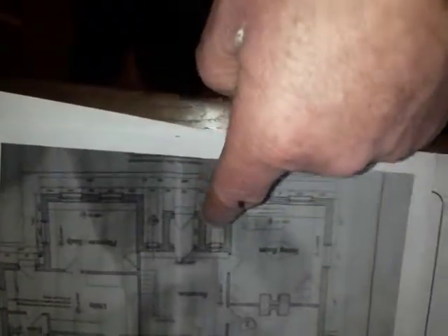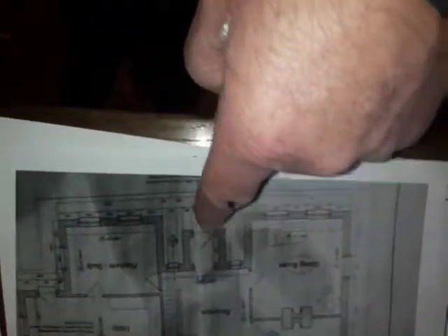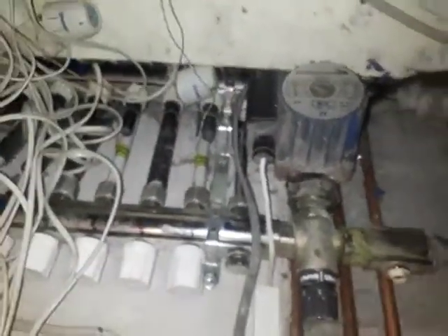Once from the temperatures we determine where the loop is actually heating in the house, we will mark that on the manifold with a permanent marker. So for example, if loop 1 for instance was the playroom study, then we take a permanent marker and we write playroom study here on one with a permanent marker so it's there forever. You do not write it on these electrical heads because they can move around. So we write it on there, and as a backup we would also mark it into the house plans here.